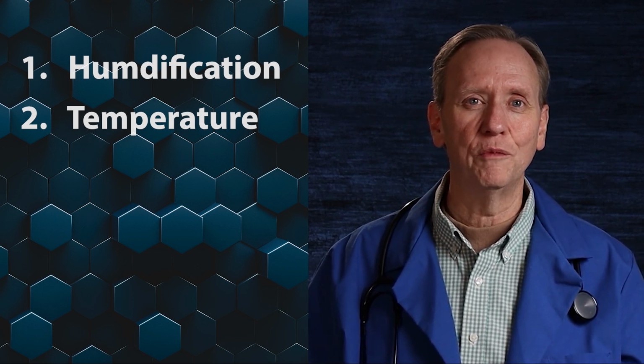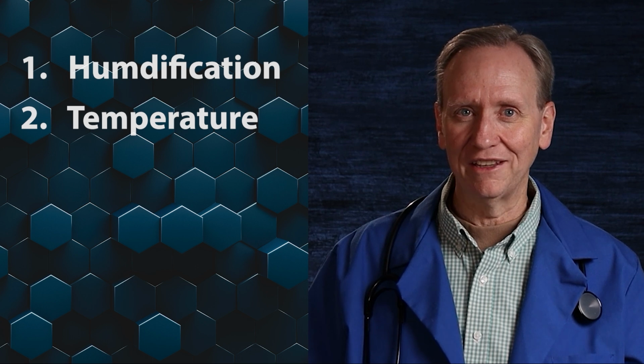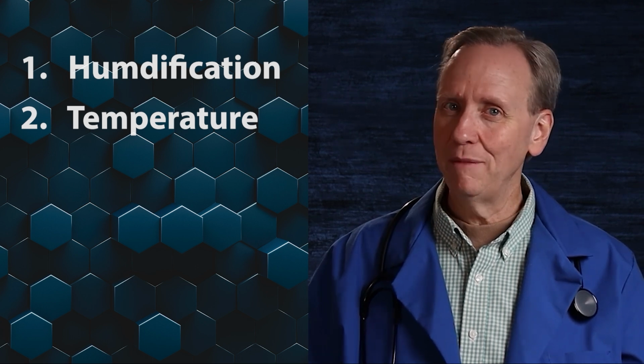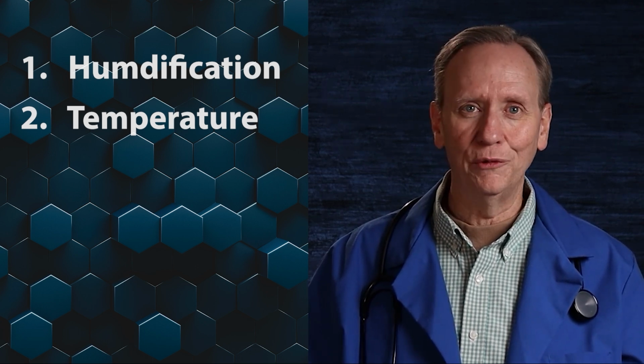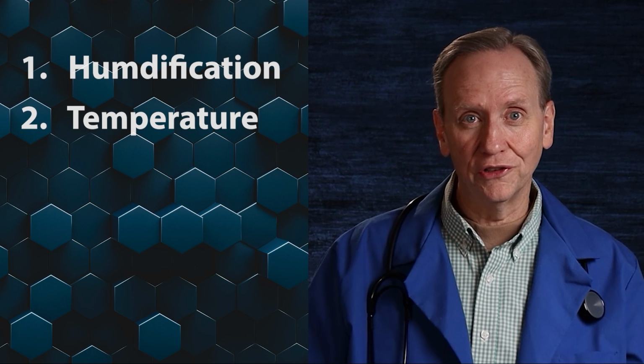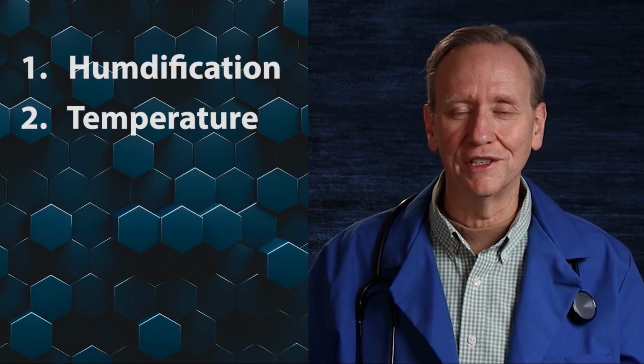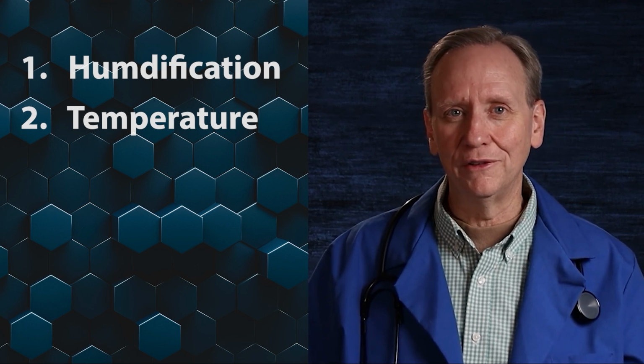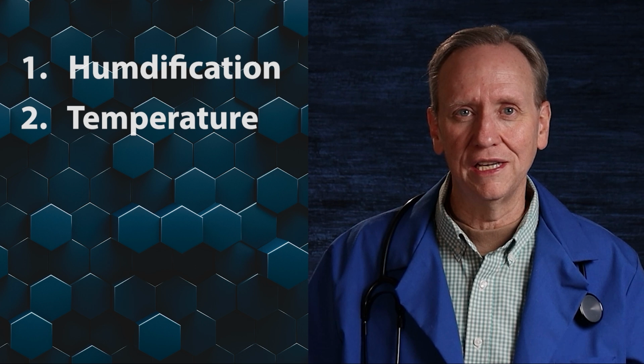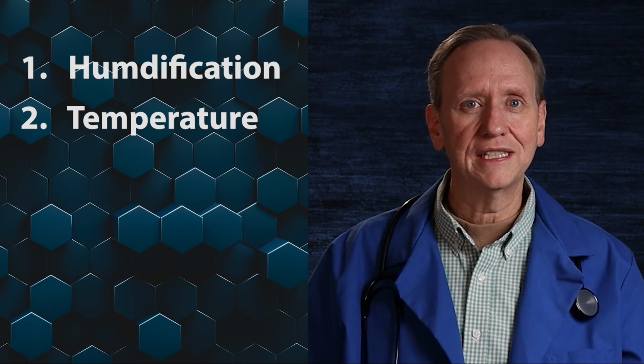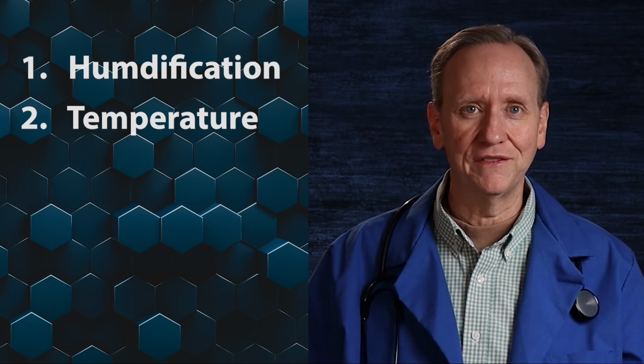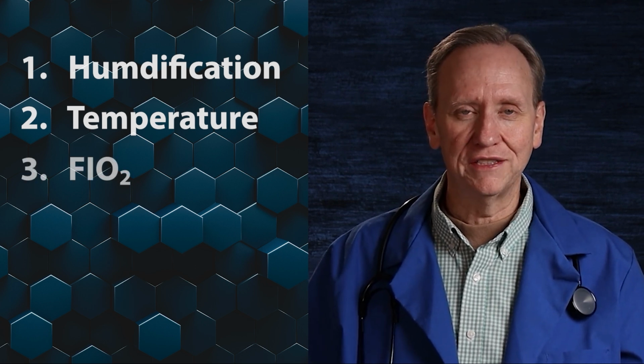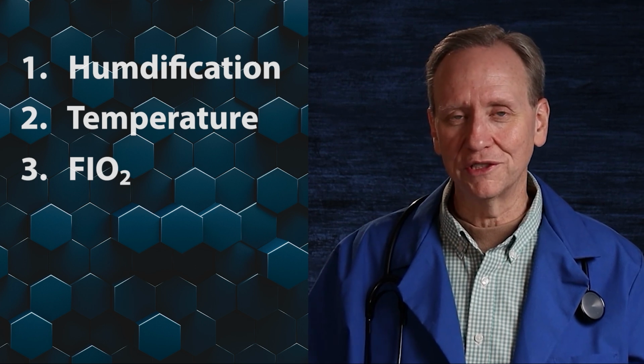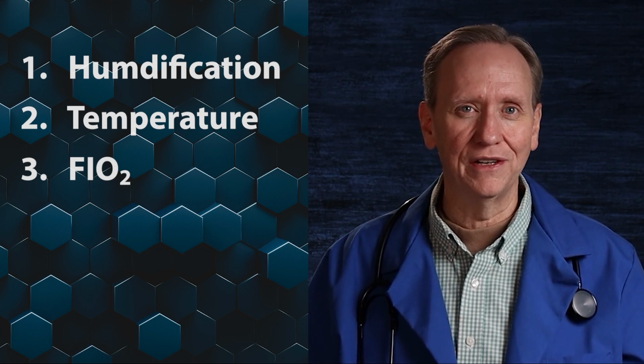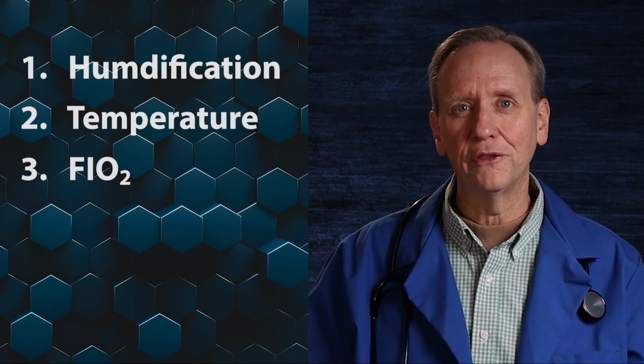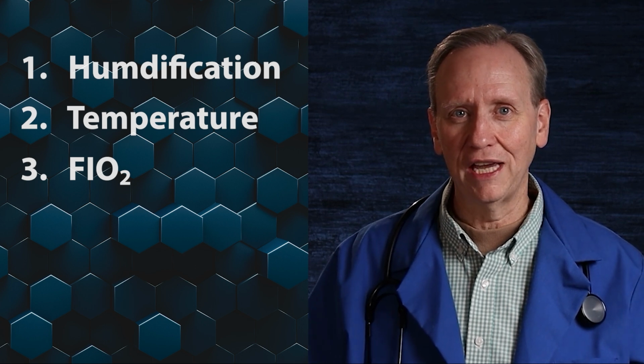And then there's a third setting that you're going to focus on, and that is because we're giving the patient so much flow, we are definitely exceeding their inspiratory demand, and that means they're not going to entrain any room air. Unlike a traditional nasal cannula where we give 2 or 3 liters and they entrain some air and they get an FiO2 of 28 to 31%, we can give 60 liters per minute at a specific FiO2. So most of these devices have some kind of a blender associated with it so you can dial in the FiO2. And that turns out to be the 3 main settings of a high-flow nasal cannula.